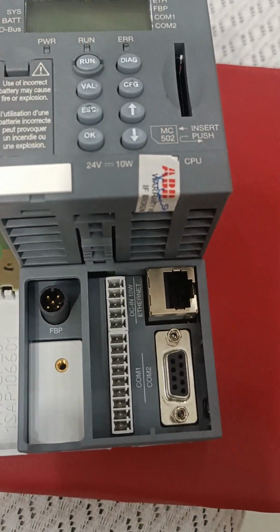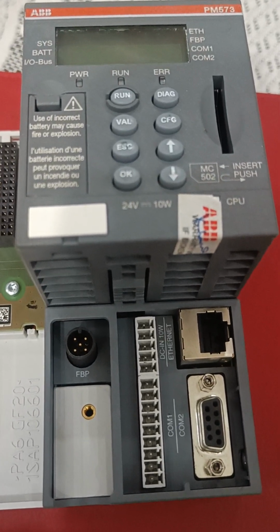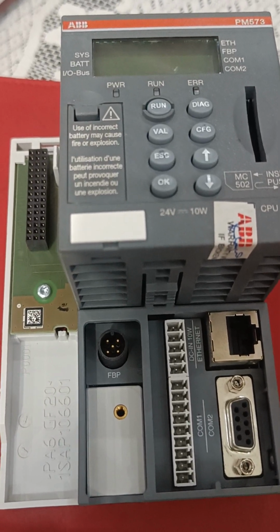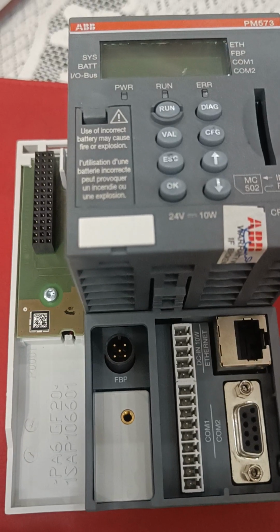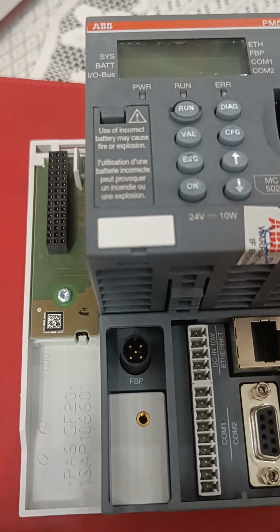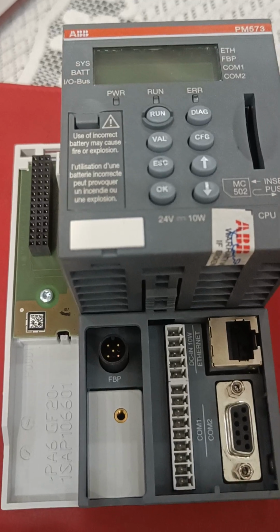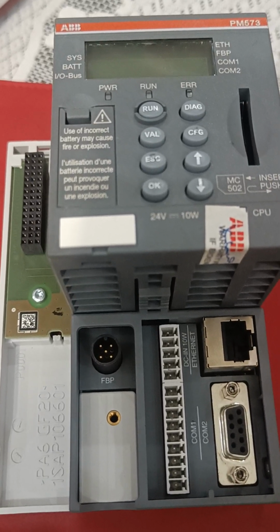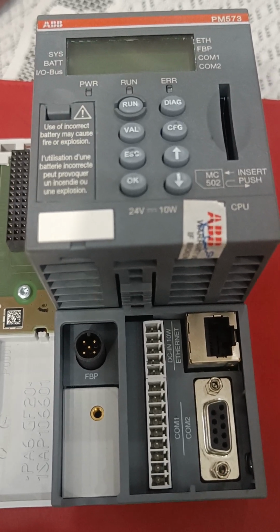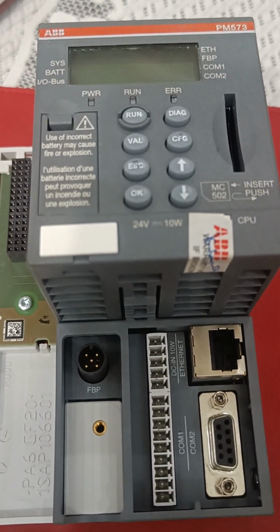Next, we will talk a little bit about performance. Boolean logic: 1000 instructions can be processed within 0.5 millisecond. Word instructions: 1000 instructions within 0.06 millisecond. Floating point instructions: 1000 instructions can be processed in 0.6 millisecond. Cycle time is user configurable, from 1 millisecond to 100 millisecond.